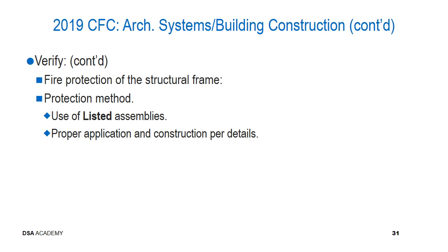Further, we want to verify that the fire protection of the structural frame has been provided: that the protection method is approved, that the use of listed assemblies has been achieved, and that the proper application and construction has been per the details.